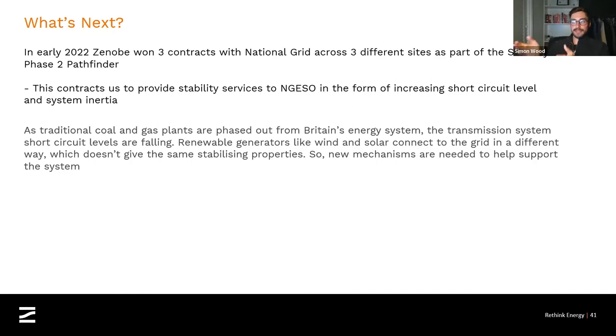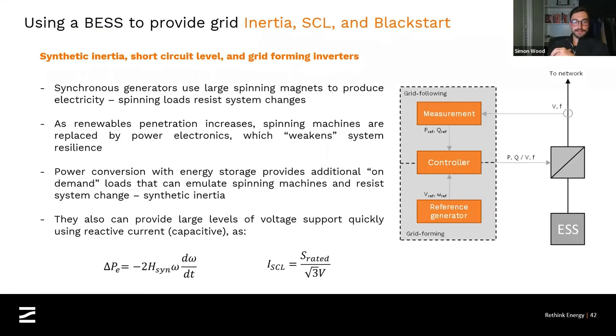Now, historically, this kind of service would be done using other forms of synchronous machines, synchronous condensers, and that kind of thing. Never before has it been done with batteries. Batteries aren't synchronous in any way. They don't have natural inertia. So that's where the importance of inverter technology comes into play. And Michael briefly explained what that means. But we've been able to demonstrate through technical studies to National Grid that actually you can provide these services with batteries. And this is how you do it.